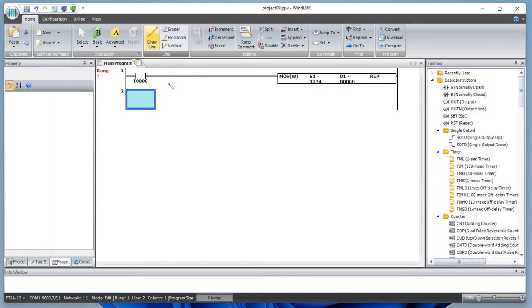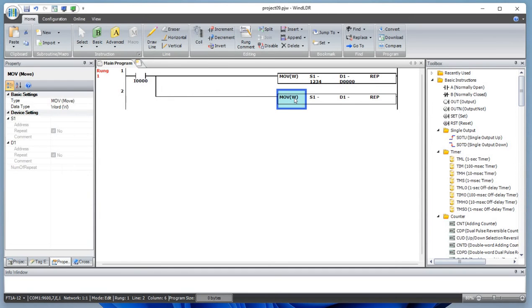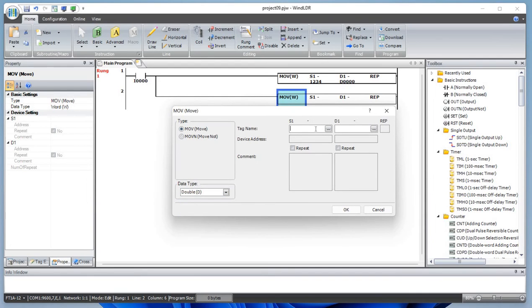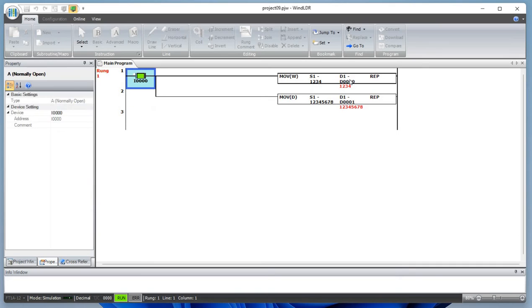Let's draw a line here and add a MOVE function, this time making it double. We will be using 12345678, and if you use D1 as the destination, that should work because it's a 32-bit double data type. Let's simulate and see what happens. Basically, the 16-bit word MOVE transfers the value 1234 from source register S1 to destination data register D0. The value 1234 has been moved from S1 to D0, and similarly for the double it's done.